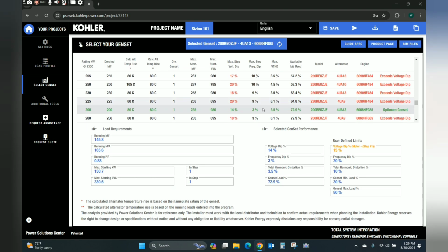If we want to put a load bank on this unit, let's say we want a minimum of about 60% runtime or percentage on it. Right now we're running at 72.9, so we're doing good there. Let me eliminate something real quick and see what comes up.